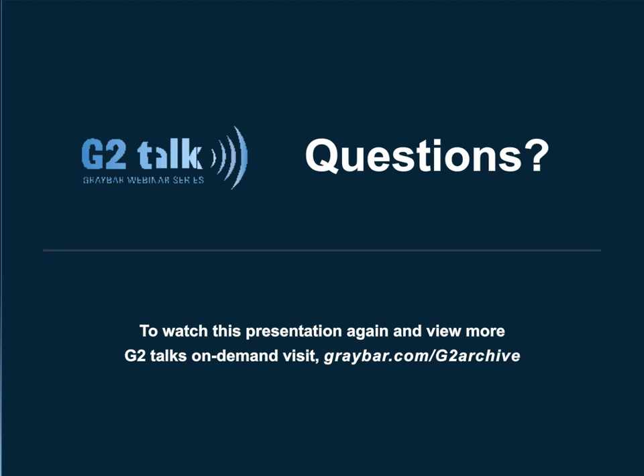Can you touch on what is the required amount of NFPA 70E training for qualified employees? Looks like that one may have been for John as well. John or Dan? No, that's for Dan. Sorry. Yes, and obviously we didn't cover all of NFPA 70E. There's a lot of training that you have to go to. What I would recommend is to get a copy of NFPA 70E, and if you go into 110.2, that covers training requirements, for both qualified and unqualified persons. With regard to the qualified person, you would go into 110.2(D)(1), and that details the training requirements for qualified people. It's an extensive list, and I don't want to read the text, but 110.2(D)(1) would be the place to go.